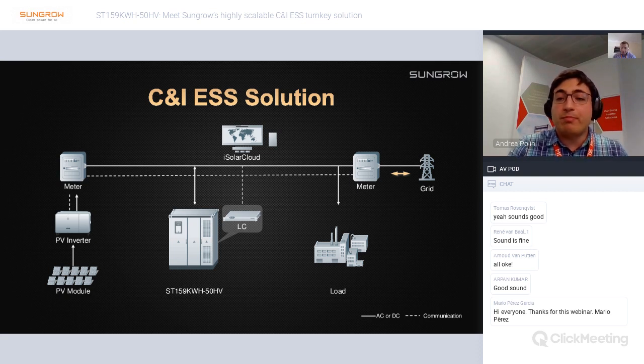If the PV generated power is higher than the load, the local controller will use the surplus energy to charge the battery. But if the PV generated power is not enough to cover the load, the local controller will discharge the battery to make sure no energy is being brought from the grid. All of this is done in real time with a very fast response, ensured by local communication between the energy meter and the local controller, and between the local controller and the PCS, to control how much power is being charged or discharged in the battery very quickly.